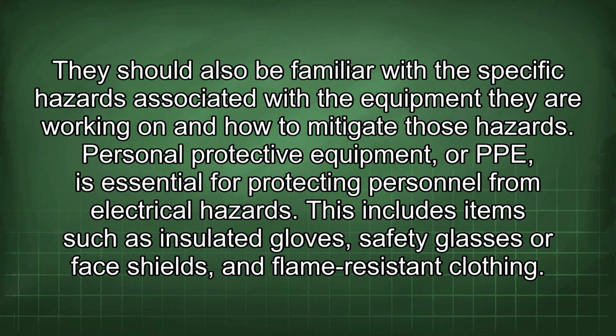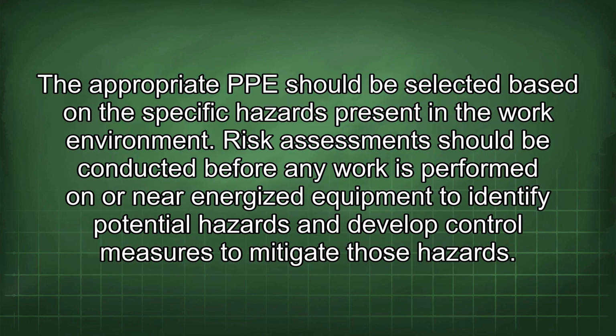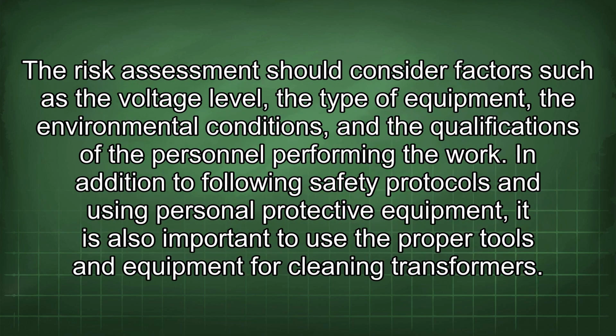Personal protective equipment, or PPE, is essential for protecting personnel from electrical hazards. This includes items such as insulated gloves, safety glasses or face shields, and flame-resistant clothing. The appropriate PPE should be selected based on the specific hazards present in the work environment. Risk assessment should be conducted before any work is performed on or near energized equipment to identify potential hazards and develop control measures to mitigate those hazards. The risk assessment should consider factors such as the voltage level, the type of equipment, the environmental conditions, and the qualifications of the personnel performing the work.